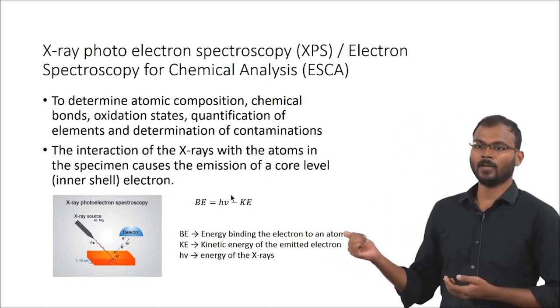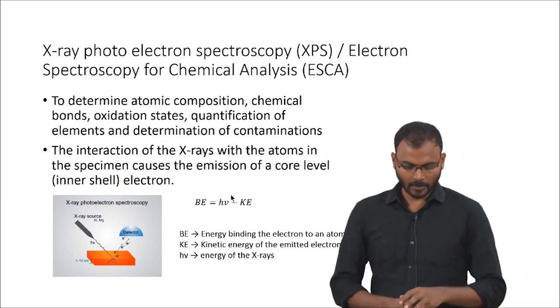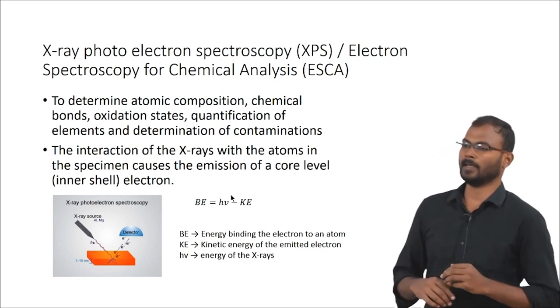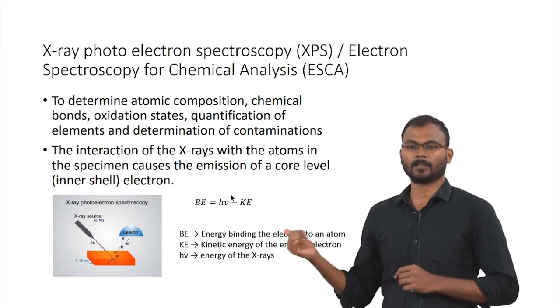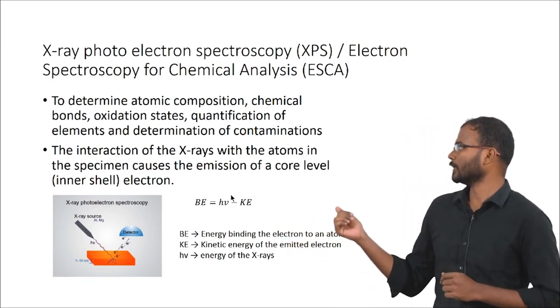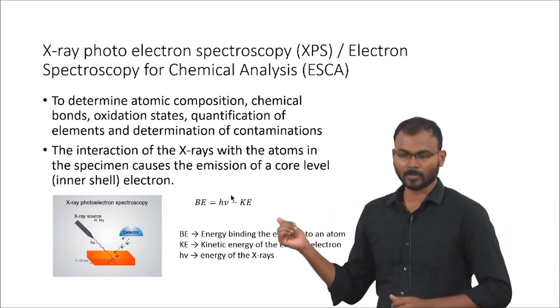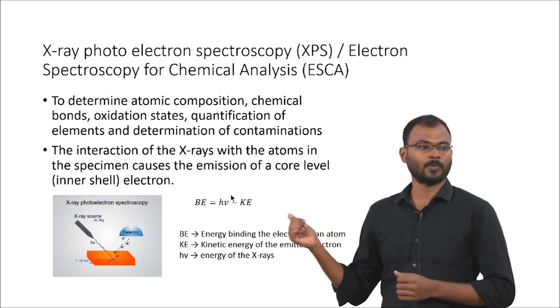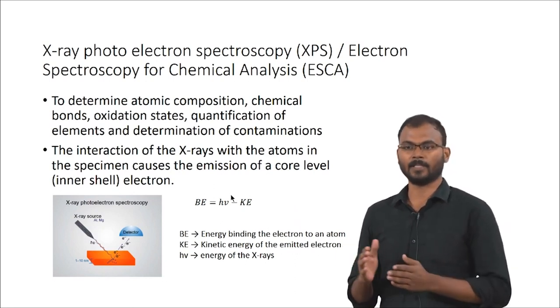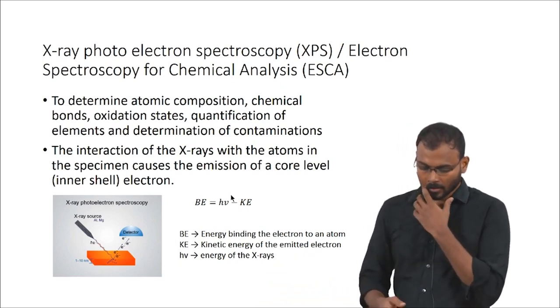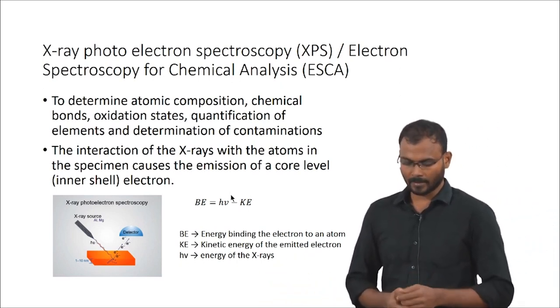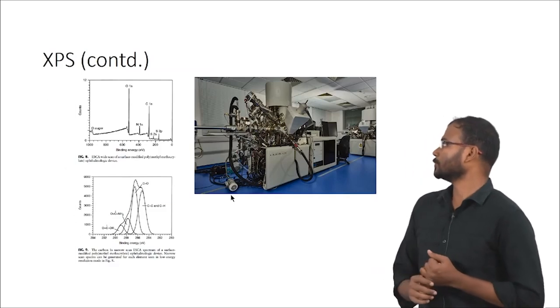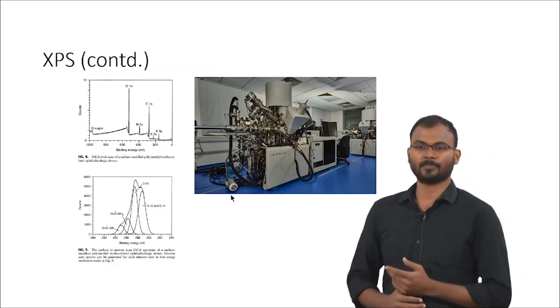XPS is mainly used when checking for contamination of a material surface or to verify whether a surface modification has had an effect. It works on the principle that when X-rays are introduced onto the surface, they excite electrons; those excited electrons are detected and their binding energy is determined based on electron intensity, identifying whether the element belongs to carbon, oxygen, nitrogen, sulfur, etc. The working principle: Binding Energy = Energy of X-rays − Kinetic Energy. This is an XPS instrument and shows how the spectrum looks.